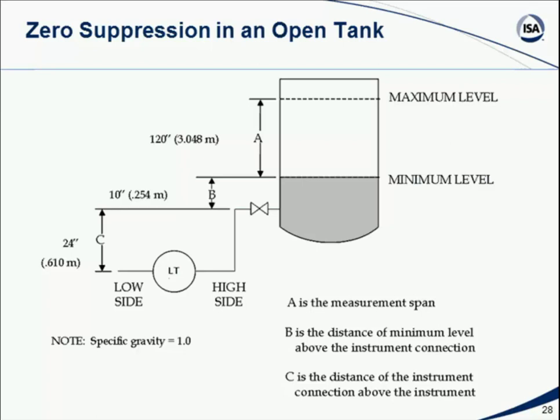But now we should also notice that on this tank, we've decided that we don't want the level to go below what's shown as the minimum level. And the minimum level is 10 inches or B above the tap point. So in fact, we would want the level indicator to show that we are at zero usable level, or 0% usable level of the tank, which doesn't mean it's empty, but we're at the minimum level when we are reading 34 inches of pressure, because we've got 10 inches above the tap and then 24 inches down to the pressure measurement device. So my zero suppression has to correct for 34 inches of fluid column. That's what I want. So when I measure actually 34 inches of pressure, that should be considered 0% tank level.